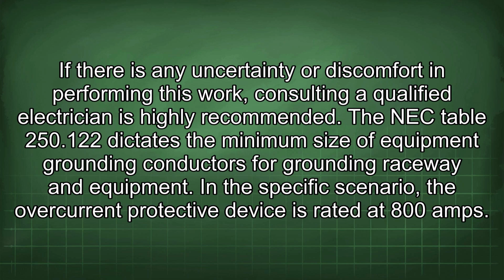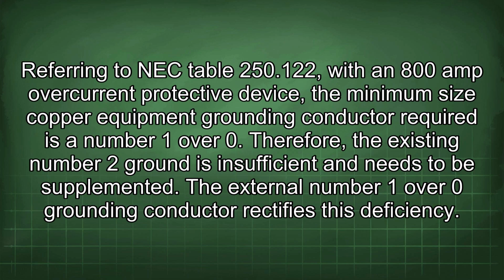The NEC Table 250.122 dictates the minimum size of equipment grounding conductors for grounding raceway and equipment. In this specific scenario, the overcurrent protective device is rated at 800 amps. Referring to NEC Table 250.122, with an 800 amp overcurrent protective device, the minimum size copper equipment grounding conductor required is a number 1/0. Therefore, the existing number 2 ground is insufficient and needs to be supplemented. The external number 1/0 grounding conductor rectifies this deficiency.